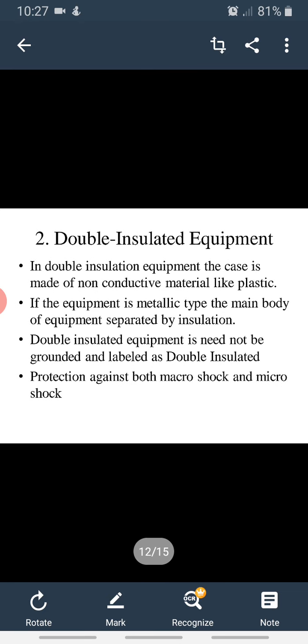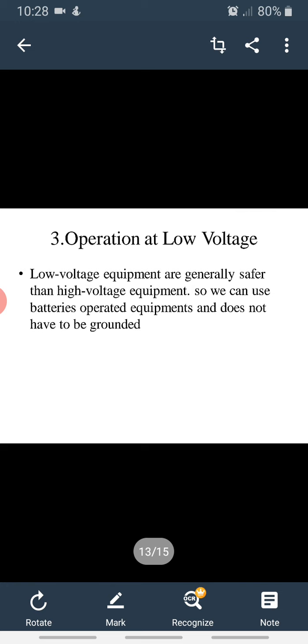And second one, double insulated equipment. In a double insulated equipment, the case is made of non-conductive material like plastic. If the equipment is metallic type, the main body of the equipment is separated by insulation. Double insulated equipment need not be grounded and is labeled as double insulated. And protection against both macro and micro shocks is possible in double insulated equipments. And third, operation at low voltage. Low voltage equipments are generally safer than high voltage equipment. So we can use battery operated equipments, which do not have to be grounded.